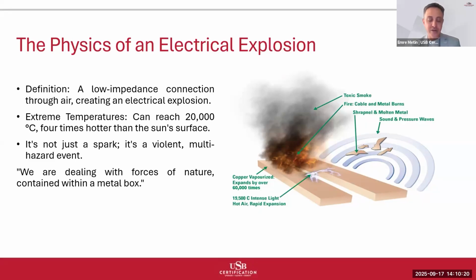After this short circuit, it ionizes the air molecules, creating a plasma channel. This plasma conducts electricity while simultaneously reaching temperatures of 20,000 degrees Celsius. To put this in perspective, that's 4 times hotter than the surface of the sun. We are literally creating a miniature star inside electrical equipment. But here's what makes this particularly dangerous. This isn't a sustained process like a furnace or welding arc. An arc flash releases this energy almost instantaneously, typically lasting anywhere from a few milliseconds to several hundred milliseconds, depending on how quickly protective devices operate.